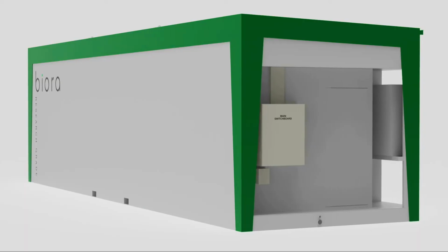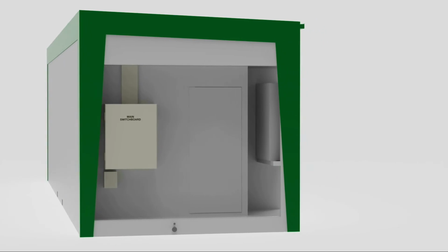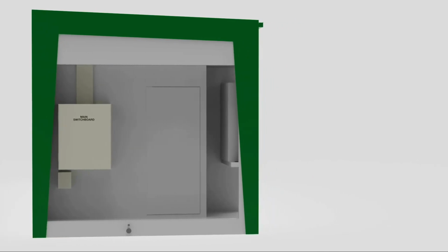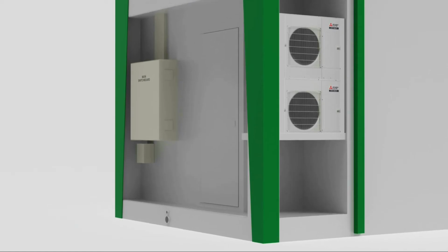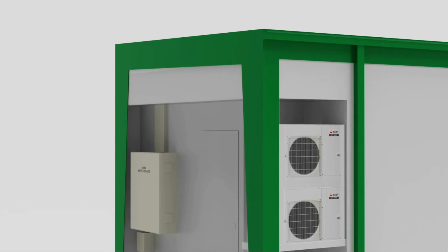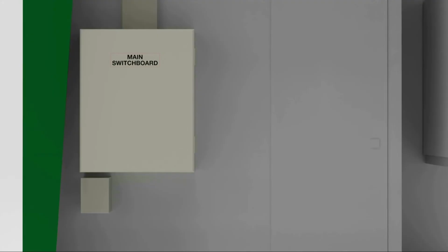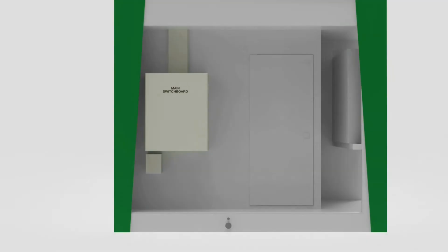The third section is the HVAC and mechanical equipment room, insulated and located at the rear of the chamber, with a separate door accessible from outside of the chamber. Temperature and humidity control equipment are all located within this zone. This room provides uniform and preconditioned air to the main room and controls temperature, relative humidity, and CO2.